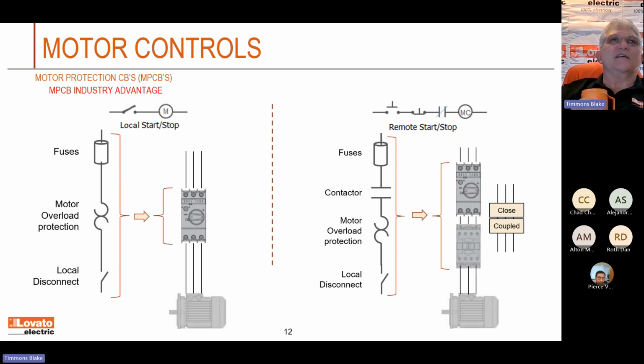Now, here are some of the advantages of using the manual motor protector. As I mentioned earlier, you can look over here to the left. Just for a local stop start, I have it at the top. But at the left, you can see you have a fuse, then a motor overload protection, and then a disconnect. Well, I've just replaced those three items with one item. So naturally, it's going to save you some labor. May even save you a little money when you add all that stuff up.